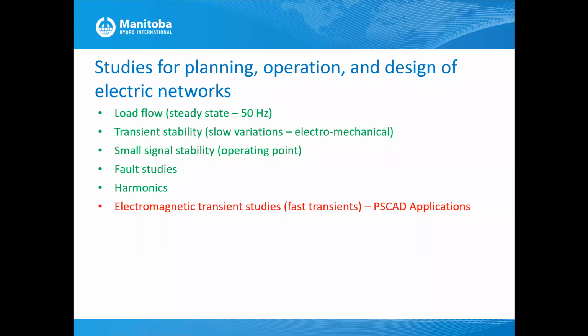System planners, operation, and transmission owners generally perform system studies in RMS tools. They typically perform load flow and transient stability, looking at electromechanical oscillations such as 0.2 to 2 Hertz, and they perform small signal analysis, eigenvalue analysis, whereby they linearize the power system at a particular operating point. They perform fault levels and typically harmonics. These are generally the studies that can be performed in RMS tools.